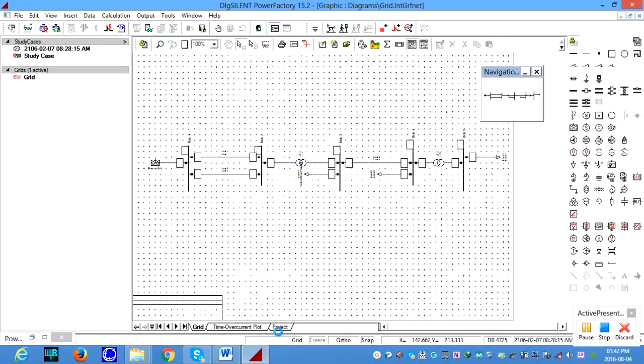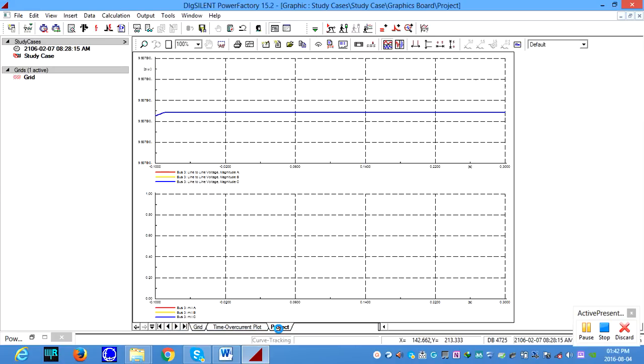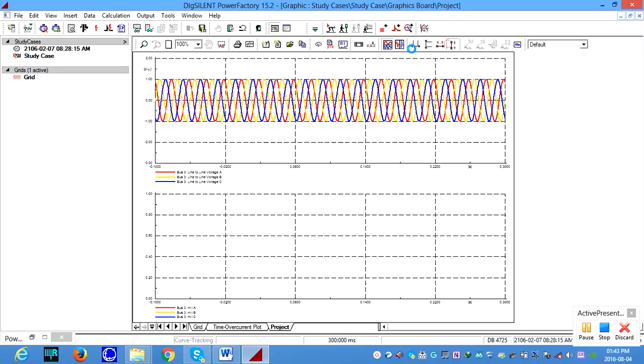So execute this one, go to the project, and again run the simulation for, let's say, 0.3 seconds. Now we're looking at auto scale. Okay, you can see we're looking at a three-phase sinusoidal RYB because there is no fault. That's why you can see there are no current waveforms here. During normal operating conditions, the system is maintaining 11 kV. So 1 per unit is 11 kV.